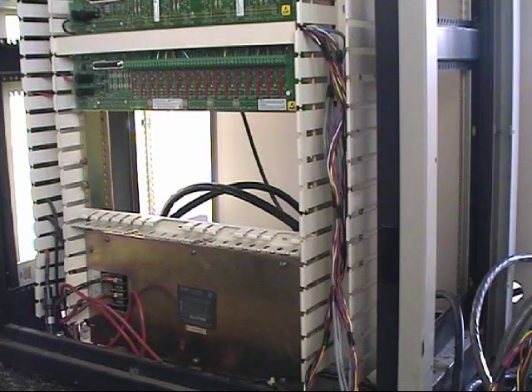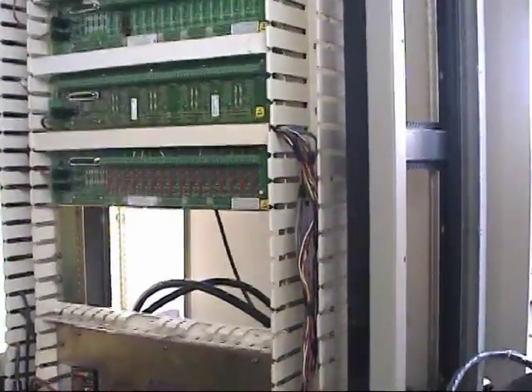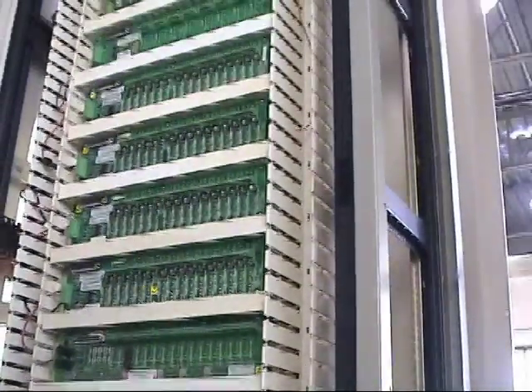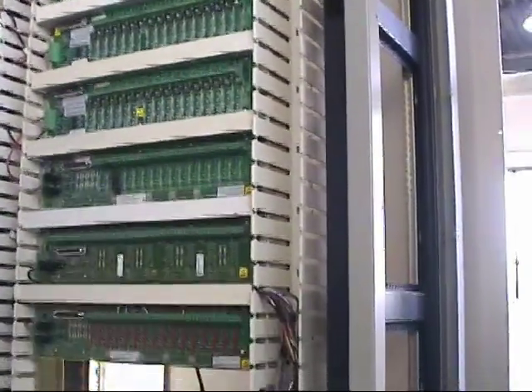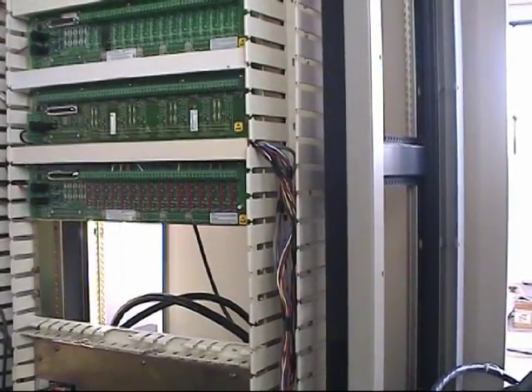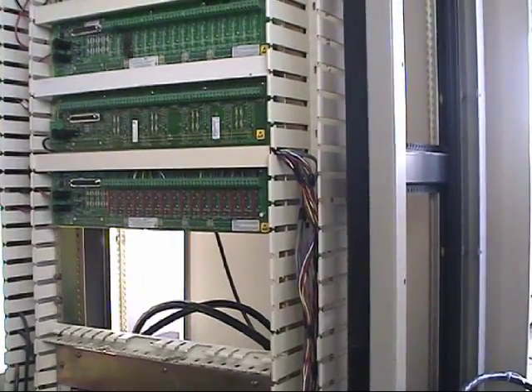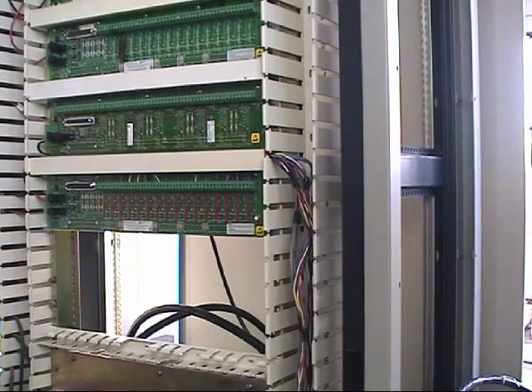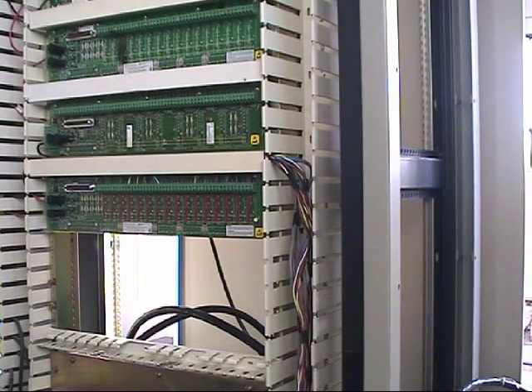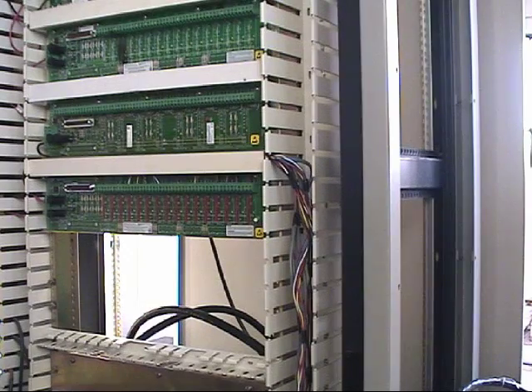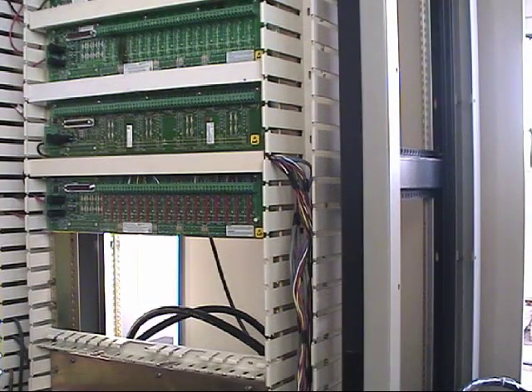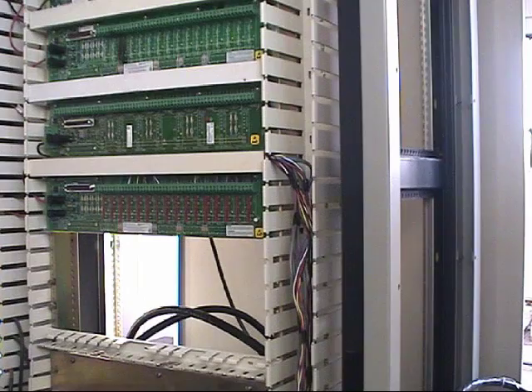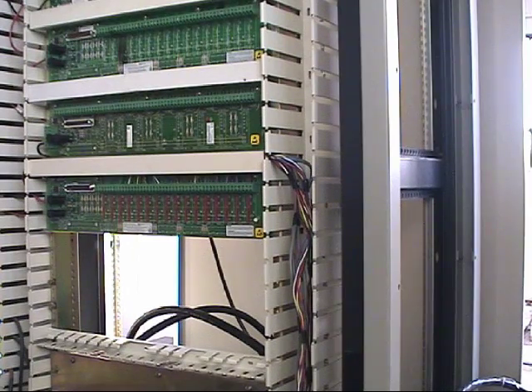Here we have a Provox cabinet that is lined with term panels from top to bottom. Since all of our wiring in this particular system comes from the bottom up, we're going to start lower than the lowest termination panel to ensure that our wires are long enough to reach all of the I.O. on the CHARMS I.O. rack.